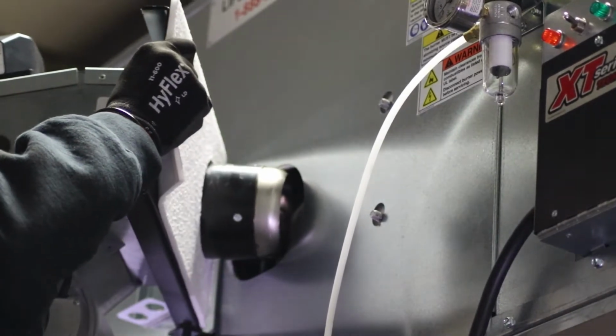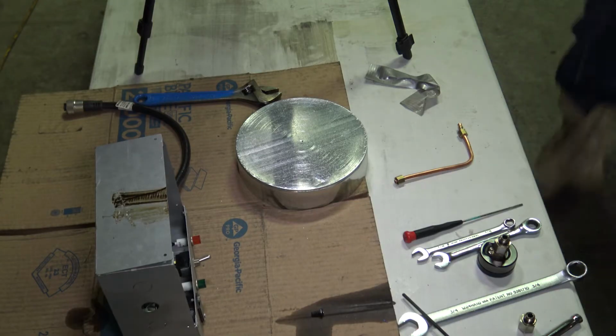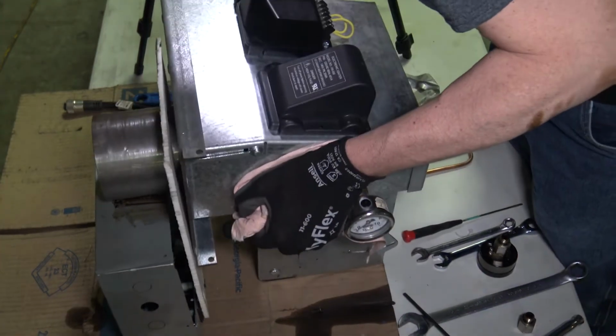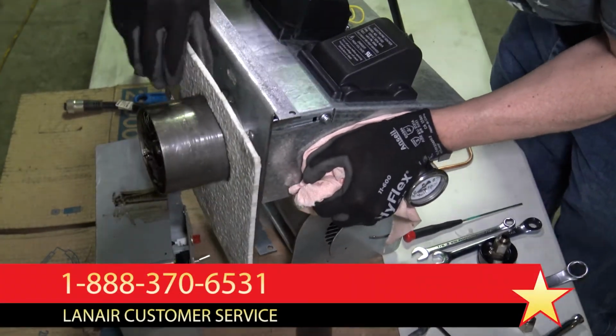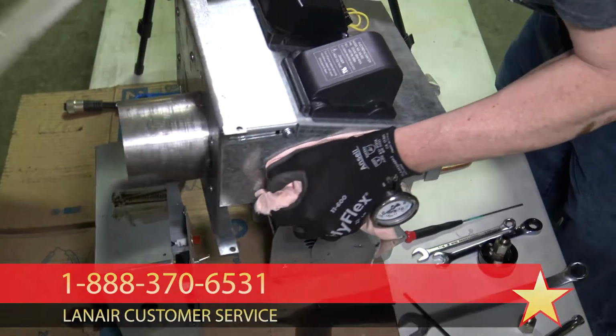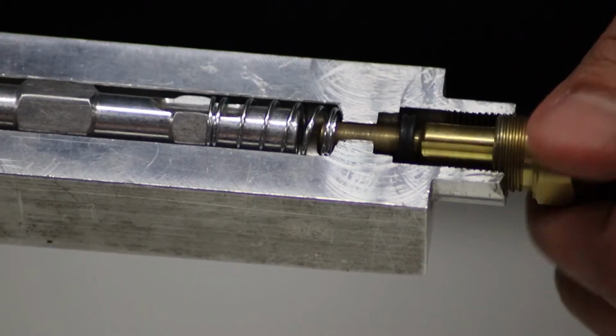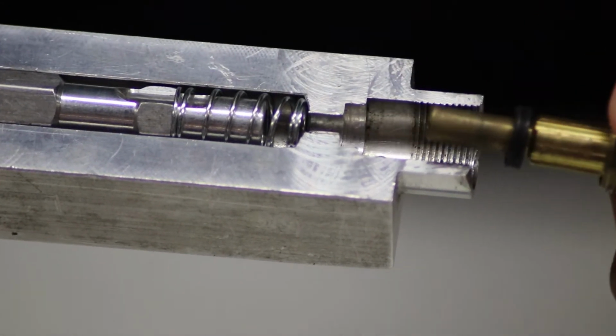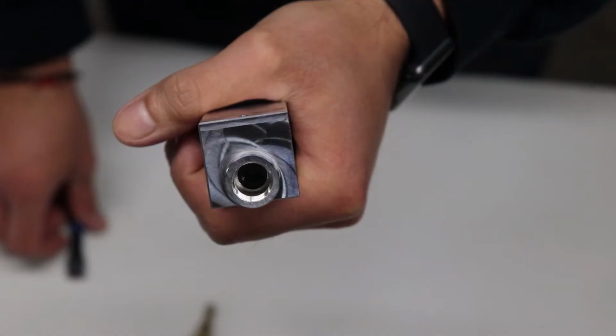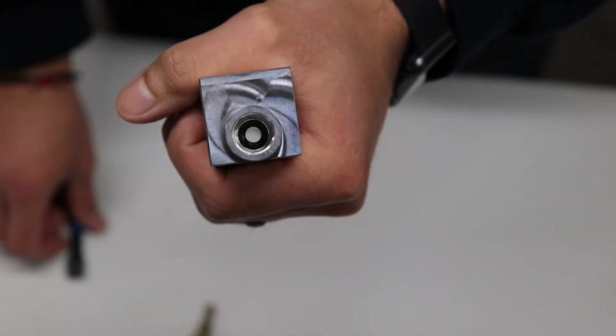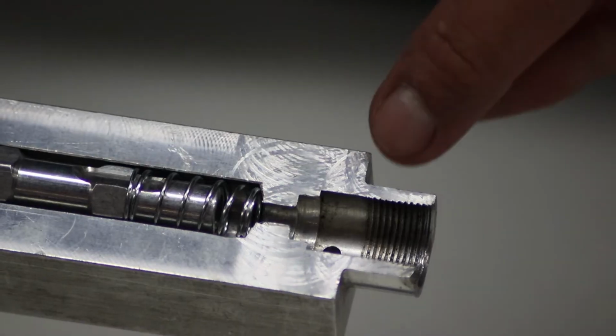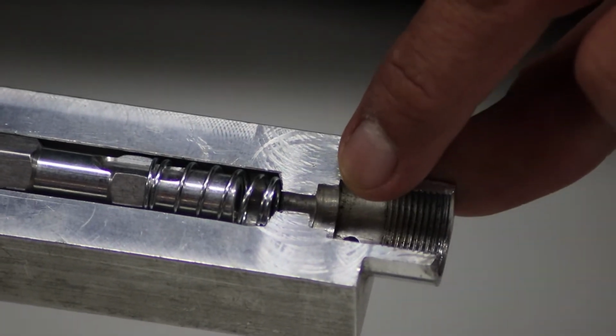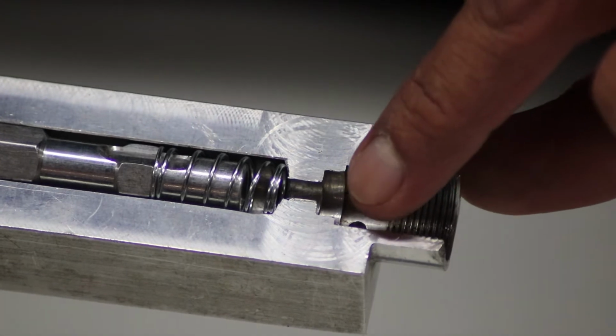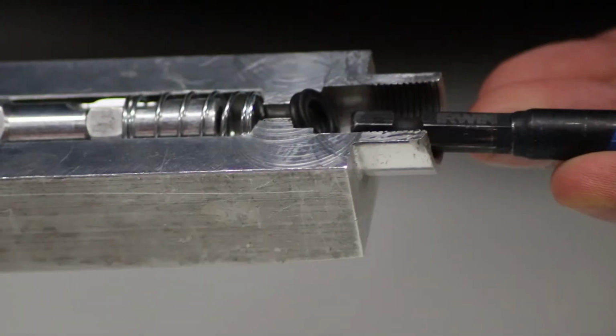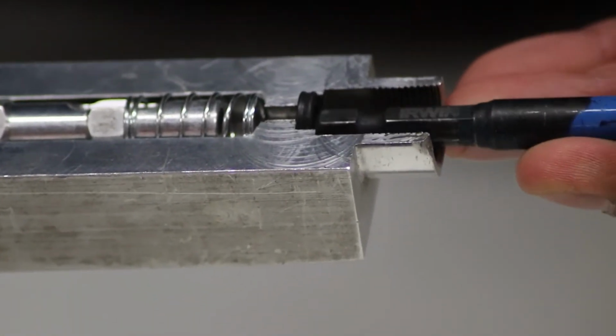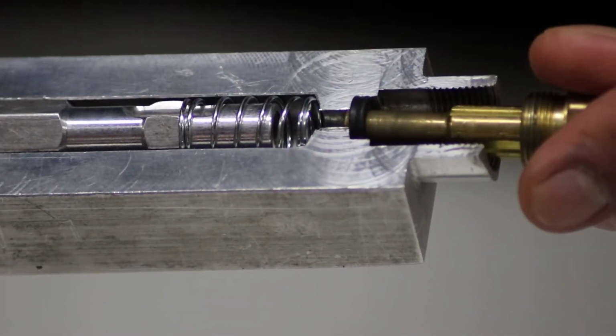If your model's burner does not have a hinge, remove the burner from the cabinet and bring it to a workbench. Replacement parts are available from Lanair customer service or at lanair.com. Being mindful not to damage or disturb the electrode tines, remove the nozzle and quad ring seal. When replacing the quad ring, it is important that it seats in the proper position within the preheater and does not become pinched or torn when installing the nozzle. For this reason, do not put the quad ring on the nozzle before installing them. Instead, install the quad ring first and confirm that it is seated correctly before installing the nozzle.